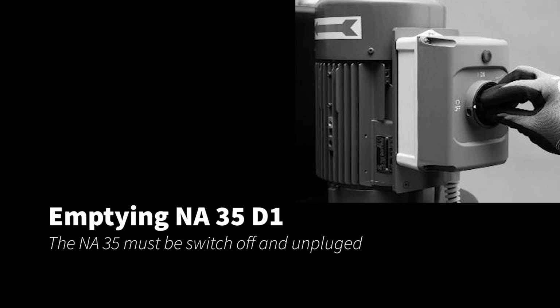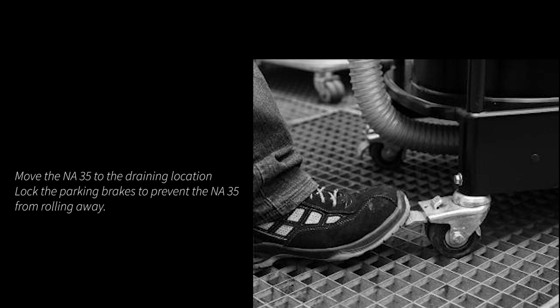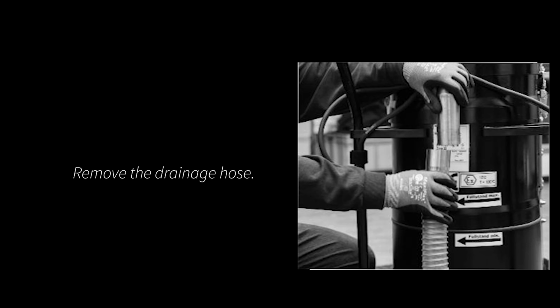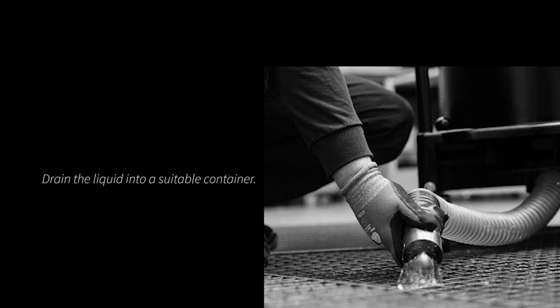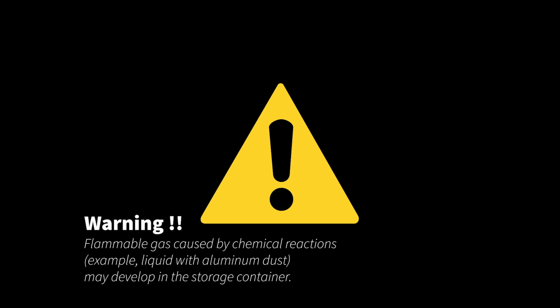Emptying the NA 35. The NA 35 must be switched off and unplugged. Move the NA 35 to the draining location. Lock the parking brakes to prevent the NA 35 from rolling away. Remove the drainage hose. Drain the liquid into a suitable container. Warning: flammable gas caused by chemical reactions, for example liquid with aluminum dust, may develop in the storage container.